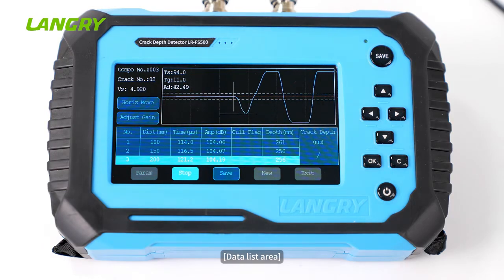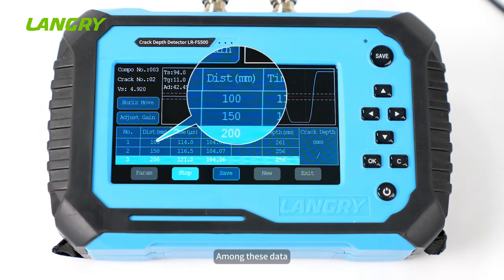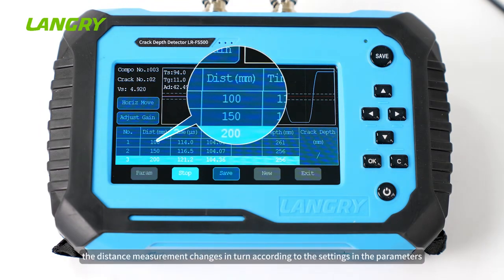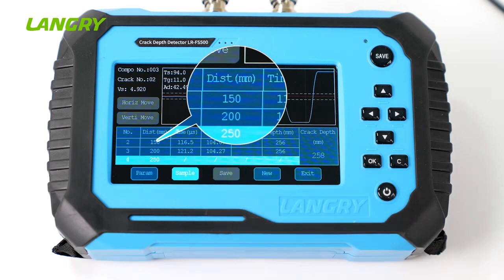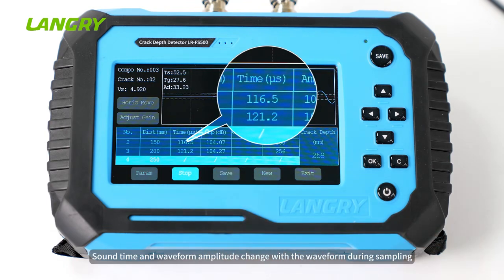Data list area. It displays the currently measured ultrasonic data. Among these data, the distance measurement changes in turn according to the settings in the parameters. Sound time and waveform amplitude change with the waveform during sampling.